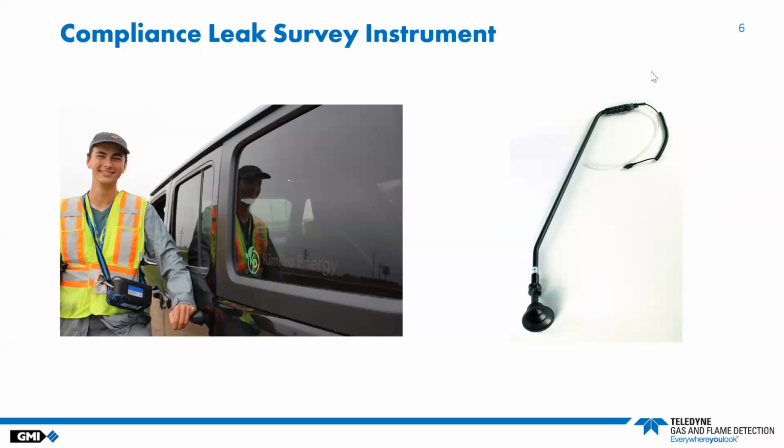With the Gas Surveyor 700, we offer two types of technologies to detect gas leaks from low-level ppm to volume gas. The infrared sensor can detect in increments of 25 ppm up to 10,000 ppm, auto-ranging in LEL, then volume gas at 1%.